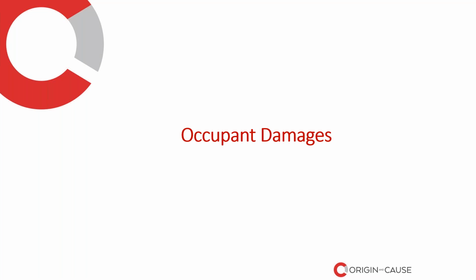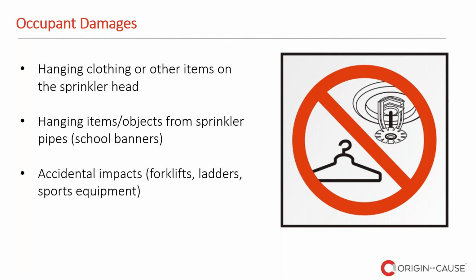Occupant damages. I recall a nice case in a downtown hotel where one of the guests, so the fire alarm activated, water started spilling out of the wall-mounted sprinkler head, and the guest ran out to the hall and said he was so sorry to have put a cloth hanger on one of the sprinkler heads. Yeah, it's very common, and what the industry has been doing in the last few years is changing some of those exposed sprinkler heads to concealed sprinkler heads. So what is happening now is you will not see the sprinkler head. It is more resilient. It is protected from damage from the occupant of the unit or the building, and they are the same. They have the same effectiveness, of course.